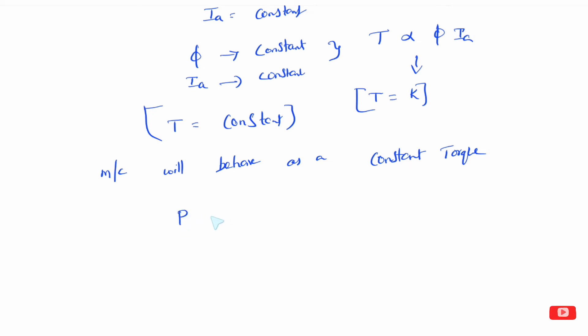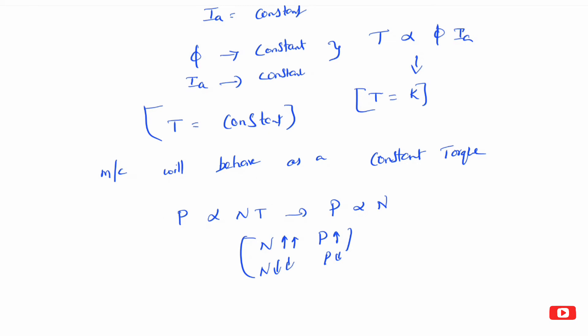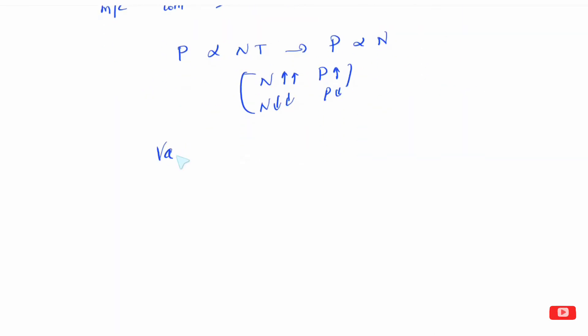Power is equal to 2π NT by 60, so power is proportional to N times T. Since torque is constant, power is proportional to N (speed). So as speed changes, power changes. This is a constant torque, variable power drive — known as a constant torque drive.